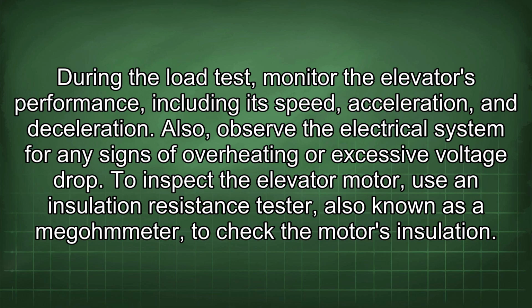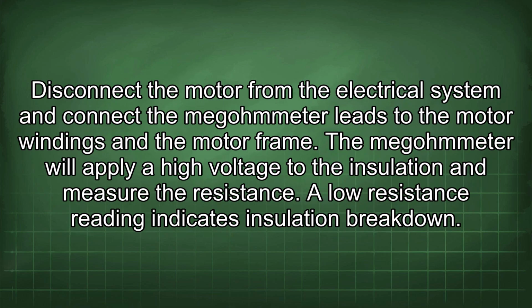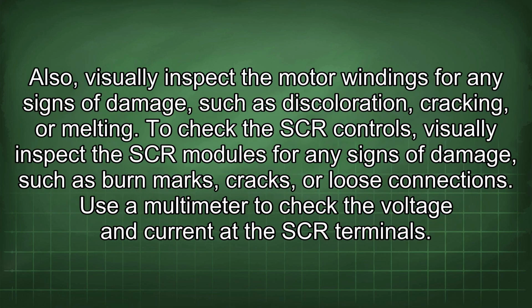To inspect the elevator motor, use an insulation resistance tester, also known as a megohmmeter, to check the motor's insulation. Disconnect the motor from the electrical system and connect the megohmmeter leads to the motor windings and the motor frame. The megohmmeter will apply a high voltage to the insulation and measure the resistance. A low resistance reading indicates insulation breakdown. Also, visually inspect the motor windings for any signs of damage, such as discoloration, cracking, or melting.